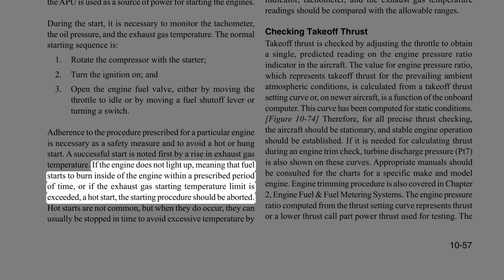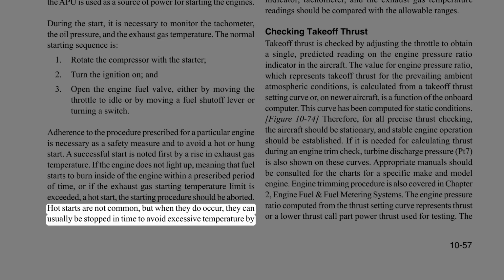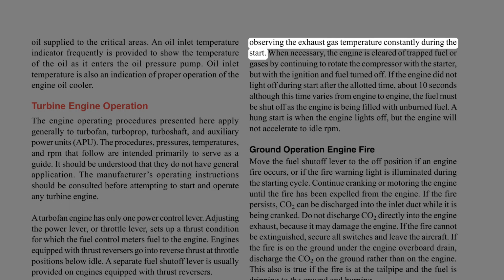If the engine does not light up, meaning that fuel starts to burn inside of the engine within a prescribed period of time, or if the exhaust gas starting temperature limit is exceeded, a hot start, the starting procedure should be aborted. Hot starts are not common, but when they do occur, they can usually be stopped in time to avoid excessive temperature by observing the exhaust gas temperature constantly during the start.